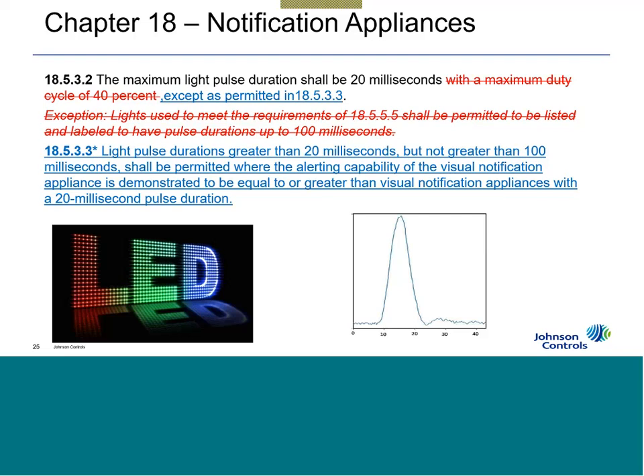So in the 2016 edition of the code, they laid the law down and said you need to have 20 millisecond pulse width for your strobes unless you're using them for 18.5.5.5, which is for hallways. In 2019, they dumped the exception and said 20 milliseconds no matter where you are. Now, the issue is there are some manufacturers on the market today in the United States that are listed that have a greater than 20 millisecond pulse width. Some of them are manufacturers that you know very well, not Johnson Controls.